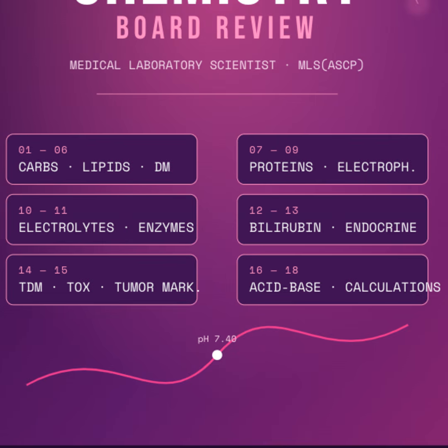The blood gas analyzer utilizes 3 distinct electrodes. First, the pH electrode. This is a specialized glass membrane electrode. The glass is formulated so that only hydrogen ions can penetrate it, creating a measurable electrical potential. Second, the PCO2 electrode, historically called the Severinghaus electrode. This is brilliantly designed. It is essentially a standard pH electrode surrounded by a weak bicarbonate buffer solution, which is enclosed in a Teflon or silicone membrane.